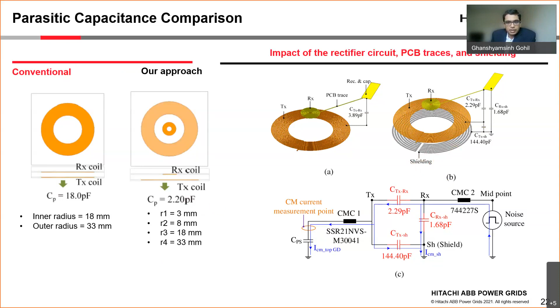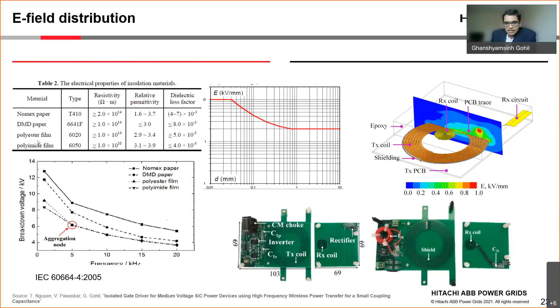Here I show the distribution of the electric field. In this case it is just over 1 kilovolt per mm, significantly lower than the dielectric strength of the epoxy we use, which is around 25 kilovolt per mm. So this can withstand high voltages while achieving small capacitance - that's the main highlight of this slide.